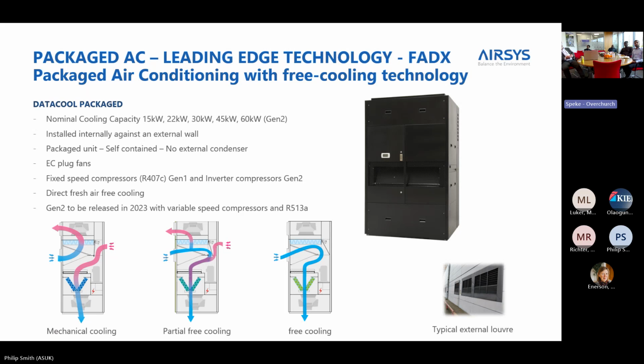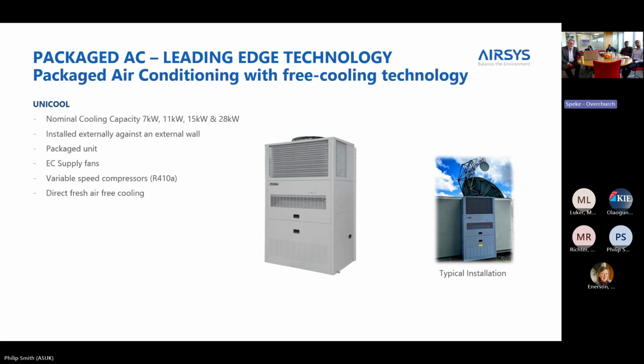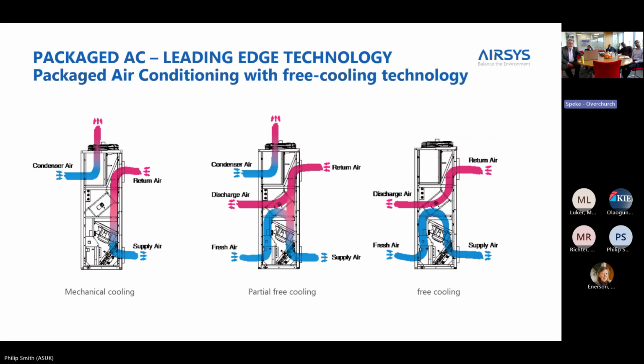On a simpler basis, we then have the more traditional vertical style fresh air DX units. We call them FADX. It's a terminology in the industry, much like calling a vacuum a hoover, for example. And again, the same principle applies, where you either bring fresh air in from outside to do your cooling, or you can bring DX in, and it will modulate throughout the year to the most efficient. These are traditionally used in exchanges, equipment rooms, UPS rooms, that sort of thing. And we can put them on the outside again, so they will sit on the outside and work in exactly the same manner.